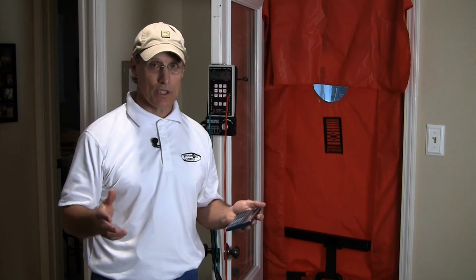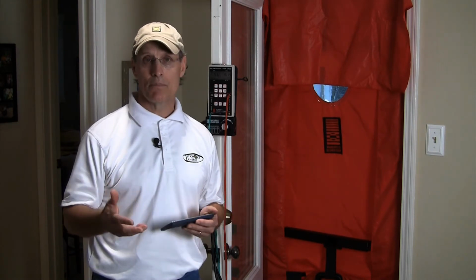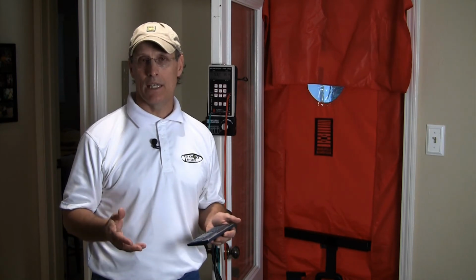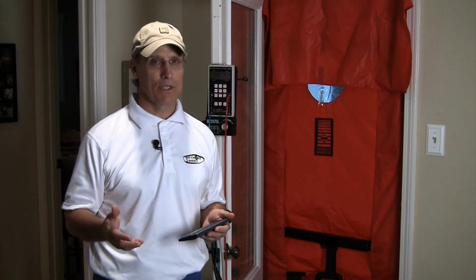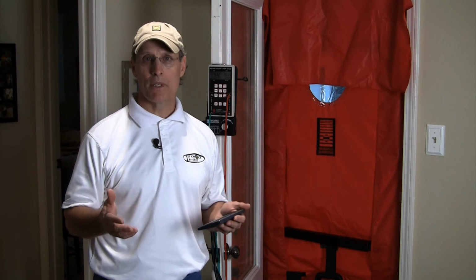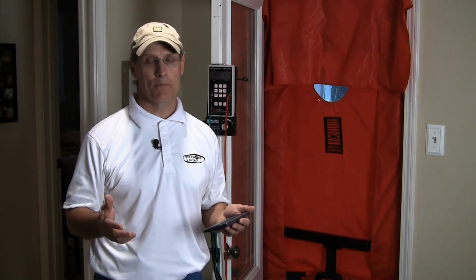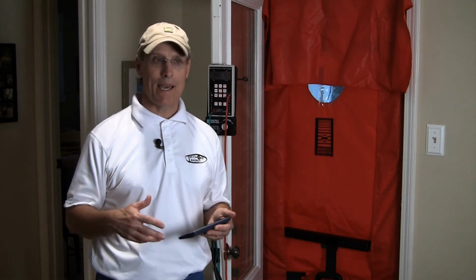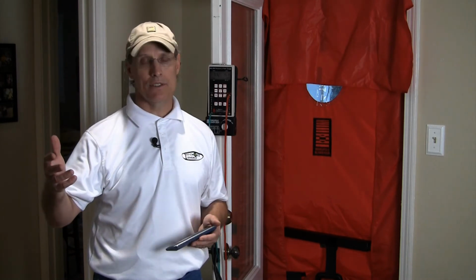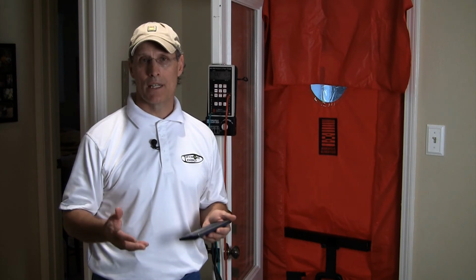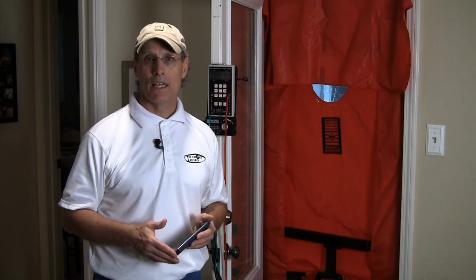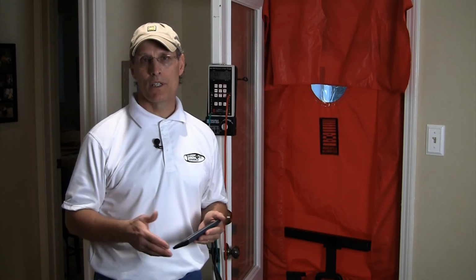And then in the process of doing the blower door test, you just walk around and find the other places in the house that are leaky, and there's just no telling where you'll find them. You can find them in some of the strangest places that people just don't expect. They can be coming out from behind cabinets, they can be coming out of closets, and then you go in and you find out that there's a defect that you never knew was there, and once you seal it, then you can improve and lower the natural air infiltration into your house and be more energy efficient.